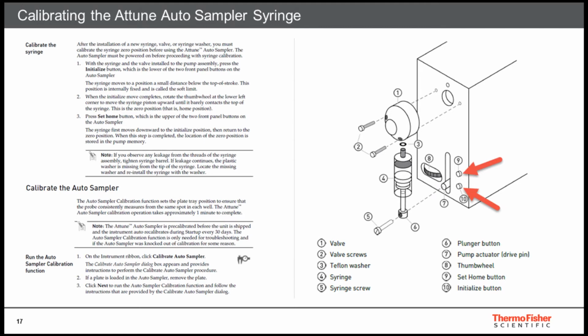Once the new syringe is installed, we have to calibrate the syringe and the autosampler. First, power on the autosampler. Then, press the initialize button, which is the lower of the two buttons located on the right of the syringe, which will cause the syringe to move down. Using the thumb wheel located on the left of the syringe, move the plunger up until the plunger basically contacts the top of the syringe. Next, press the set home button, which is the upper of the two buttons located on the right of the syringe when facing the autosampler. Now, the hard part is done. We just have to go through the regular Autosampler and Attune power cycle.